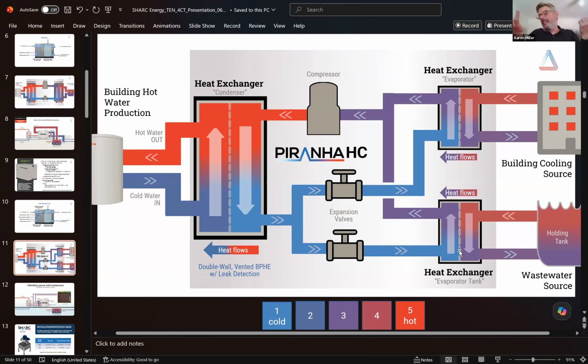Let's say the tank's at 68 degrees, but it's the middle of the winter time, and everybody in their apartments is taking energy out of that geo loop to heat their apartments. So that loop is really, really cold, right? 45 degrees. Well, we don't want to touch that. We don't want to get too close to freezing. So we'll just pull off the sanitary tank.